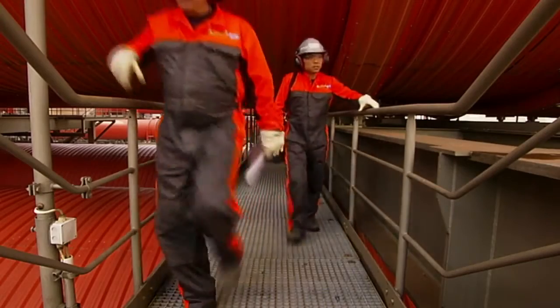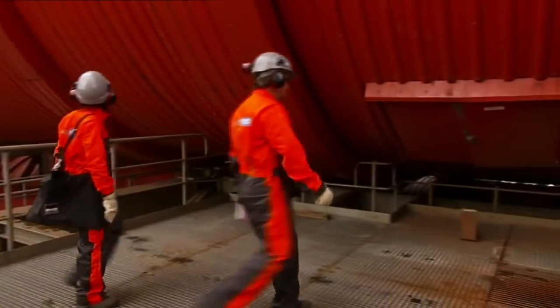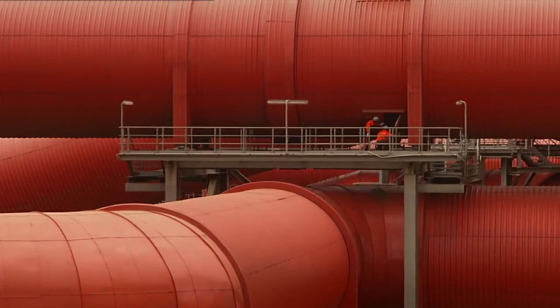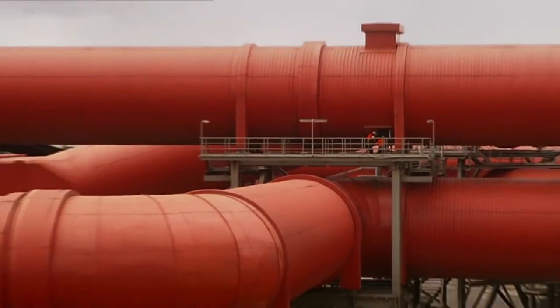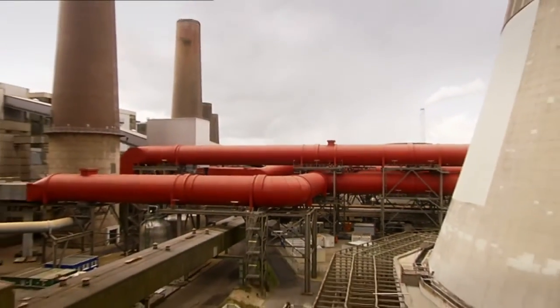Frequent inspection should be done of the flue gas channels to ensure there's no indication of defects in the insulation. The use of process safety management or PSM and regular visual inspection can prevent minor irregularities from going undetected and becoming a costly issue.